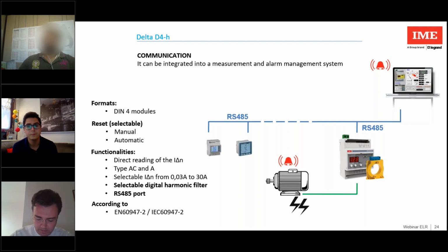From Carlos: is there any standard that we should follow regarding the way to pass the cable through the toroid, for example, that defines the distance to internal toroids? No, there isn't a generic rule. You have to choose the differential toroid so that all the cable or busbar passes easily. You don't have to constrict the cable to the toroid, but leave more or less one or two fingers between the cable and the toroid, and center the cable.